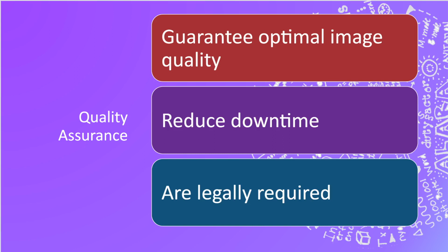Now, another thing it's going to do is reduce downtime. And that might seem odd at first, thinking, well, you're blocking the schedule, you have to make sure you have access to the machine. Well, no, it actually does reduce downtime, because if you're scanning a patient and you realize your machine doesn't work, it takes a lot longer to get biomed in there or get a physicist in there to look at your machine. It takes more energy to cancel all those patients because now you're down the machine. So it's really important that we are catching any of those small things sooner so we can fix them when we have the time versus having it be kind of like an emergency later on.